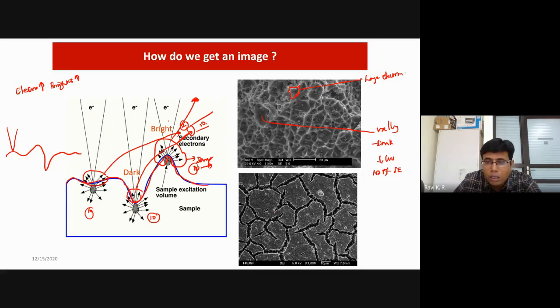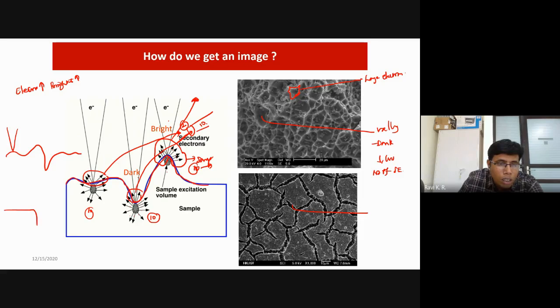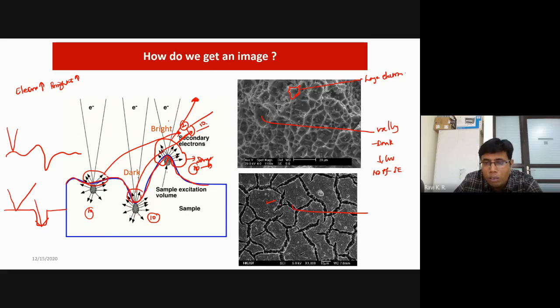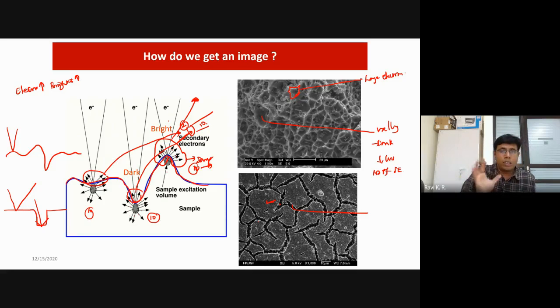This is one of the most important imaging modes in SEM — it's a simple mode. Using secondary electrons gives you morphology. Whatever morphology you see in your electron microscope image comes from this fundamental contrast mechanism. Dark regions are pits or valleys where electrons get trapped and fewer reach the detector; bright regions are raised peaks where more electrons escape.